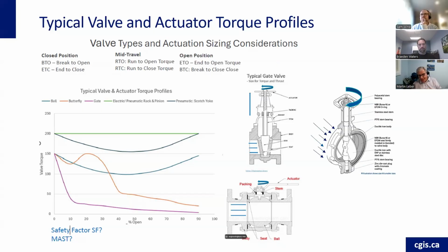What is super critical is that the sizing of the actuator does not exceed MAST. We could have a webinar just on sizing and selection, but the key is ensuring that the maximum allowable stem torque is not exceeded. And if it's an electric application, you want to make sure that if the actuator stalls, that is, when the torque switch is bypassed and the motor sees a stall condition, the torque created in that scenario does not exceed the MAST condition. Again, it depends on the application, and there may be applications where you may be sizing with a factor of safety of 1.5 or even 2 times, depending on the environment.